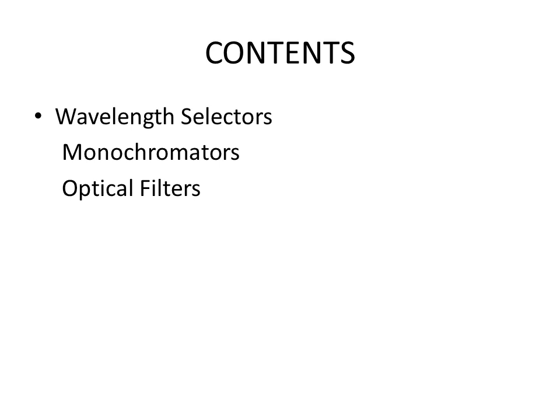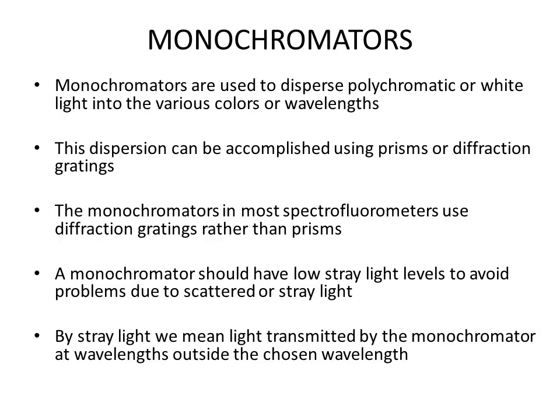In this video we'll discuss the wavelength selectors. Monochromators and optical filters are used as wavelength selectors. Fluorometers use optical filters while spectrofluorometers use monochromators, though some spectrofluorometers use both. We'll now see both monochromators and optical filters in detail. First, monochromators are used to disperse polychromatic or white light into various colors or wavelengths.